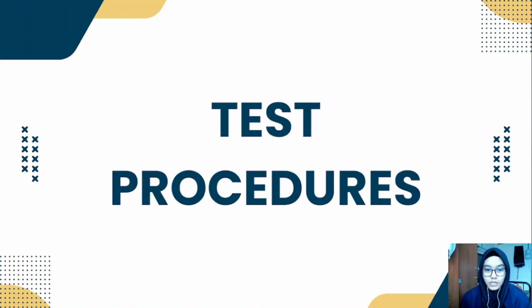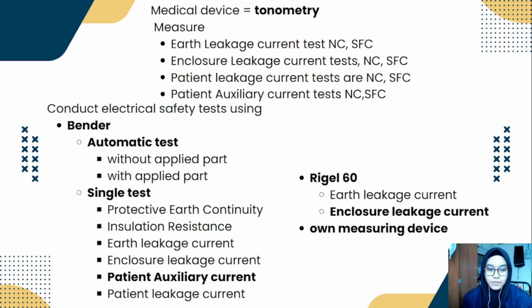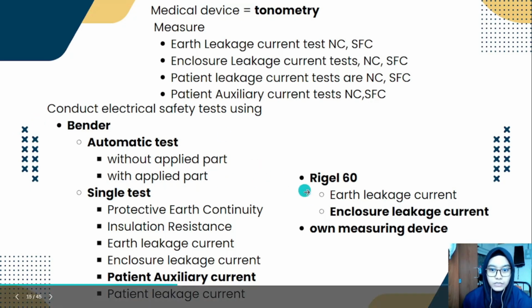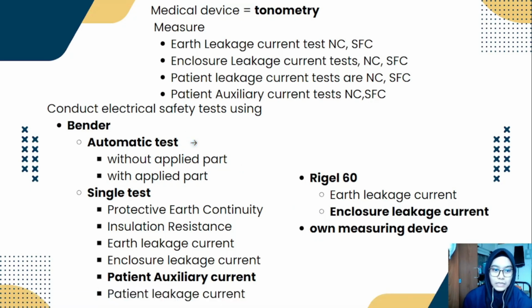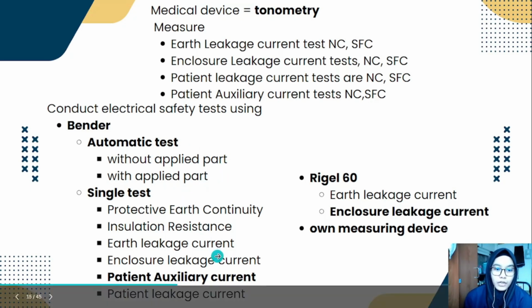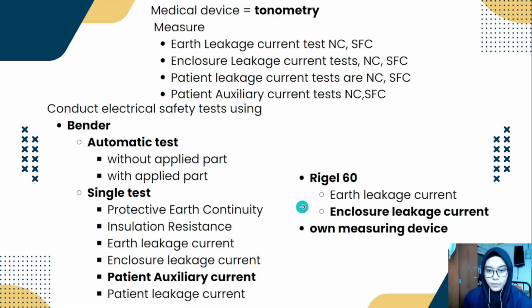Next, we can proceed to the test procedure. For this safety test, our medical device is the tonometer, and we need to measure the earth leakage current, enclosure leakage current, patient leakage current, and patient auxiliary current for the normal condition and single fault condition. So we conduct the electrical safety test using Bender, Rigel 60, and our own measuring device. For Bender, we use the automatic test and the single test. For the automatic test, we have without applied part and with applied part, and for the single test, we only find the patient auxiliary current. And for the Rigel 60, we only measure the enclosure leakage current.